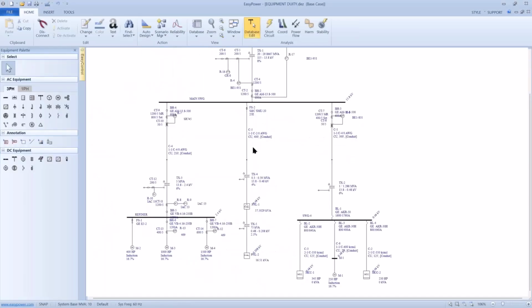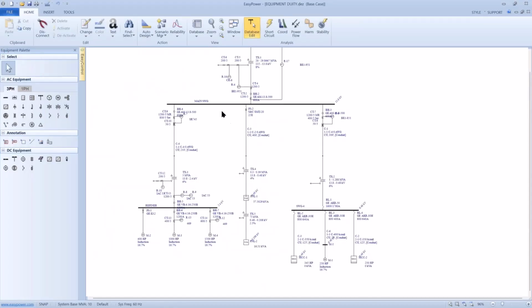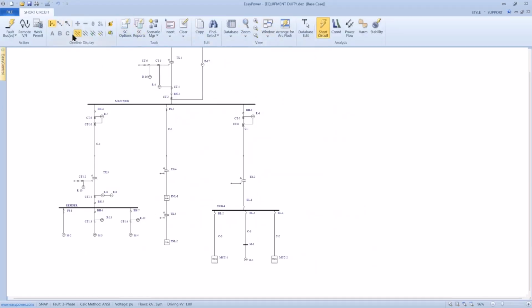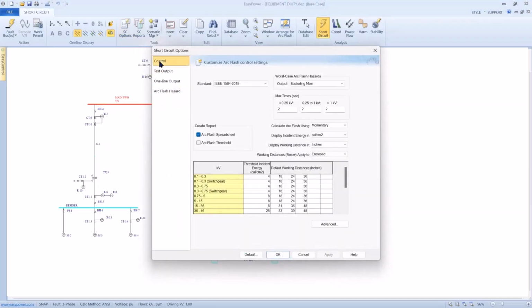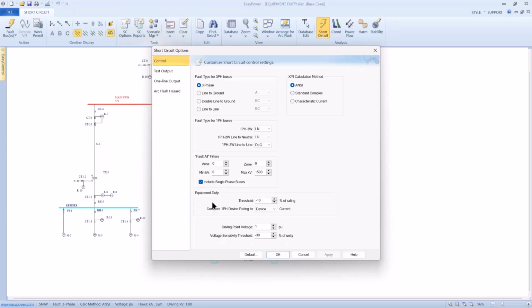Okay, so what is being done when I click on equipment duty? Just so you know, if I go to short circuit focus, looking at three-phase bolted fault on all the buses, that illuminates this little token on the second row called equipment duty. When I click on that, it applies a measurement against the threshold for every one of these devices. That threshold is determined under short circuit options, down in the bottom third, and by default we set a threshold of negative 10% from the manufacturer's datasheet rating, and then flag the results.